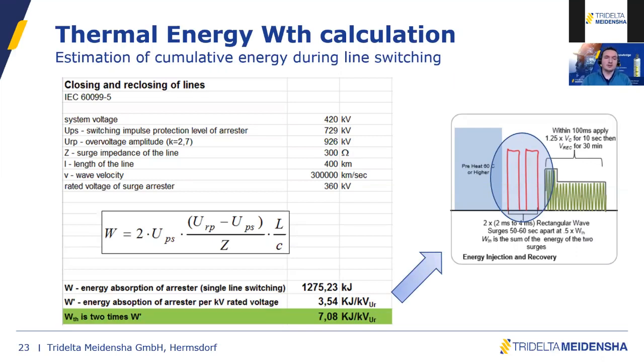There is also a formula in the -5 that I mentioned. If you want more details, there is an annex in the -5 that gives you all the important information to make such a calculation, and what is needed for your system. Today, most power utilities and consultants use PSCAD or EMTP software to run such simulations, so you don't need to do it manually. There was also a change in the new IEC standards because those requirements come from the power utilities, who sometimes work with consultants doing such simulations.